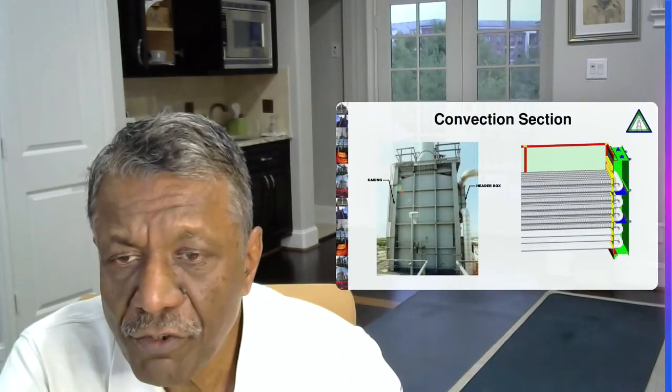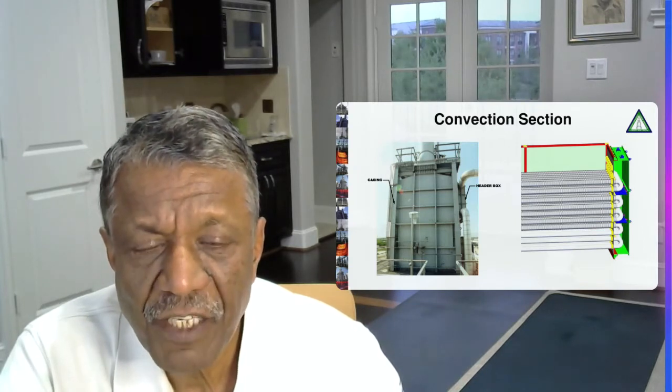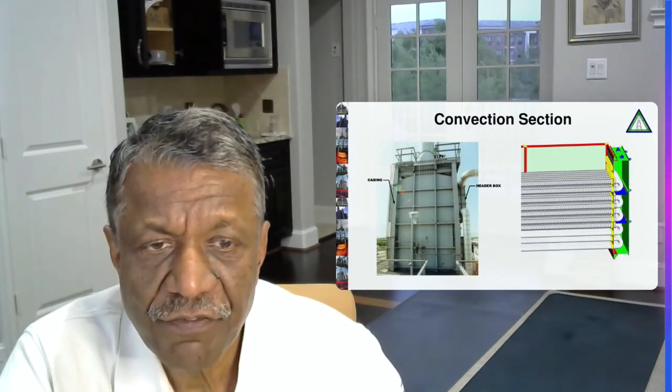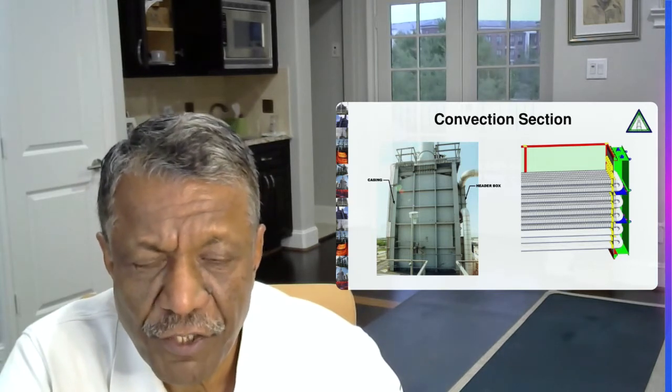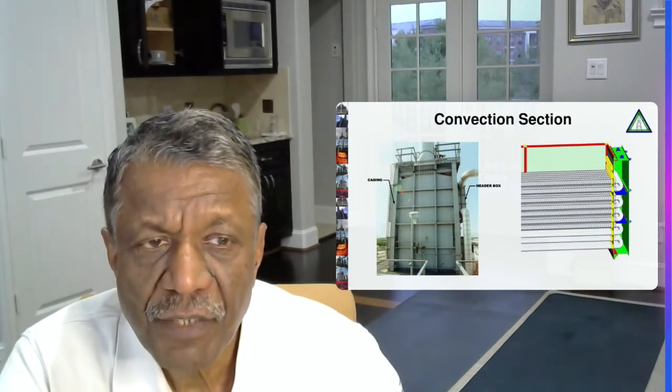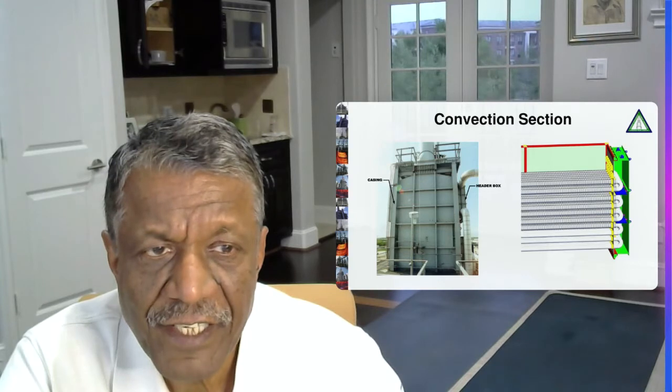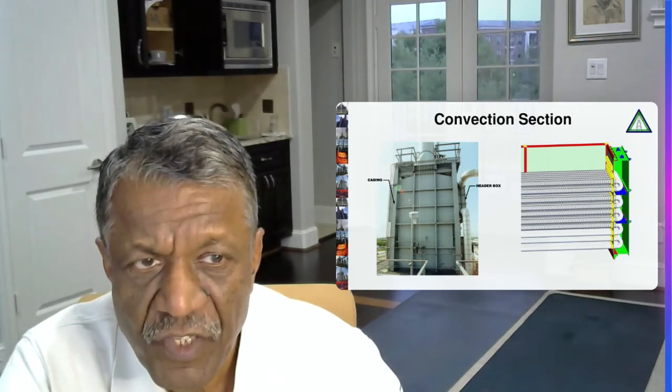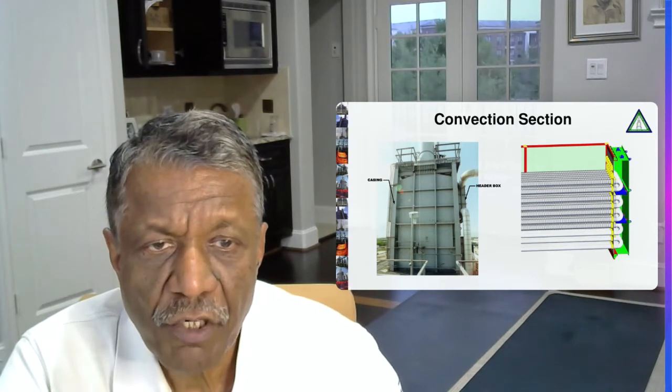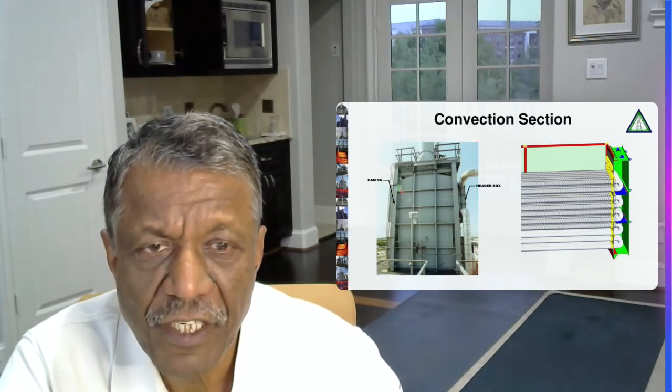Convection section is the second most important component in the fired heater. Here the heat is recovered from the flue gases by means of flue gas velocity. So typically we will have three rows of bare tubes which are known as shield tubes or shock tubes, followed by fin or studded tubes where the heat is recovered. The tubes are mostly arranged in triangular pitch and we have the return bends housed in a header box so that the flue gases don't flow through the return bends. The header boxes are on both sides, so there is a cross flow. The flue gases are flowing from bottom to top and the fluid is flowing from top to bottom in a counter current manner, and that's how the heat is transferred.